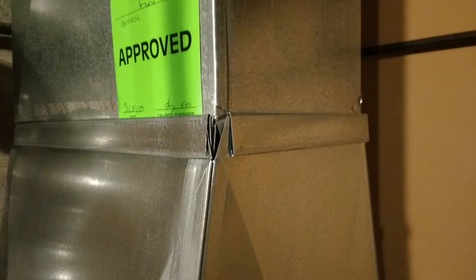Here's an example. Now this is a replacement furnace. The transition on the bottom is brand new, meeting the old return at the top. The locks are in place, but you can see the leaks. And the inspector looked at it and approved it. Didn't need to be sealed, apparently. Now, on a new system, it does need to be sealed, certainly. But apparently, given this approval sticker, a replacement system does not need to be sealed. However, there's always a benefit to sealing.